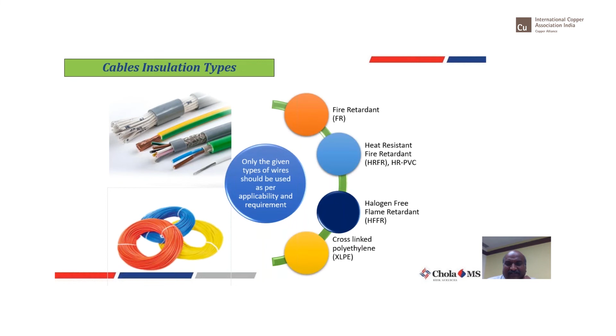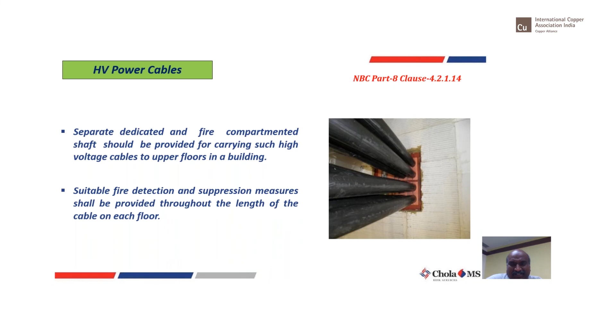So cable insulation, depending upon the usage, you can select either FR or HR and PVC, halogen free and XLP cables which are there in the market. So you can select the right ones. With respect to power cables, yes, have separations, have partition walls between one location to the other, and use suitable fire detection and suppression measures so that the cables do not get damaged.